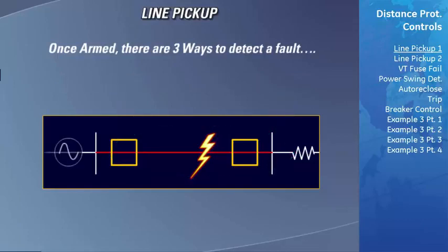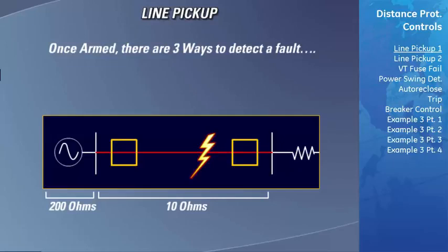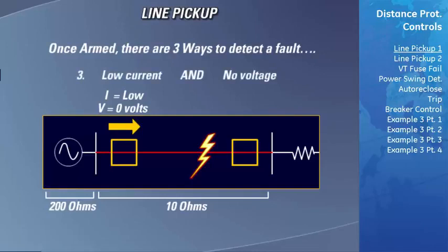The third method the line pickup element uses to detect a breaker closing in on a fault is used for transmission lines that are being fed from a weak source. If the breaker is closed onto a fault on a transmission line that has a high system impedance ratio, the current will be relatively low and the voltage will be measured as essentially 0 volts. In this scenario, none of the two methods described before will pick up because of this very low current level. Therefore, for this method, the line pickup element will use the internal line pickup instantaneous overcurrent element to monitor for the presence of low current flow and no voltage. If it detects both of these criteria, it will signal the D60 to trip the breaker.